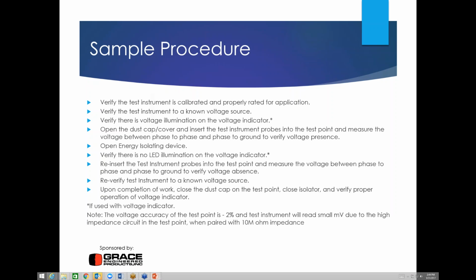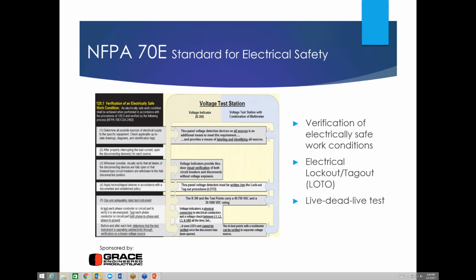Here's how it all comes together and meets the current standard for NFPA 70E for creating an electrically safe work condition. And you'll see the requirements there on the left-hand side, from 120.1 all the way up through 120.5, and how the voltage indicator, the voltage test station or test points themselves, along with your current multimeter, meet the requirements for creating an electrically safe work environment.